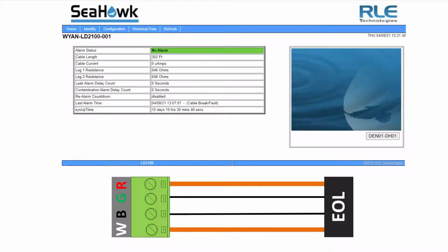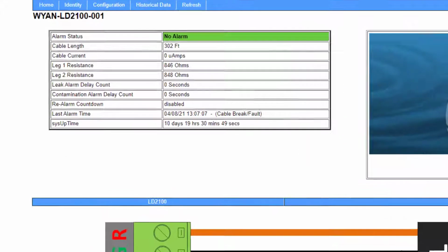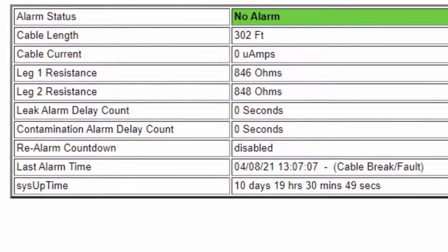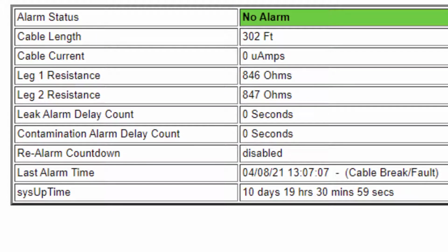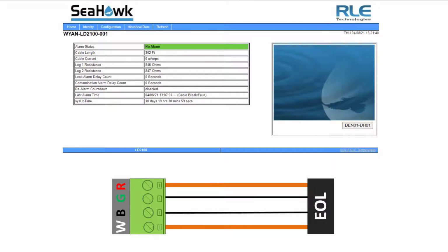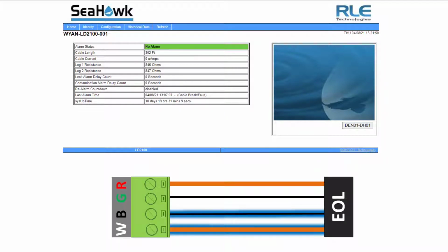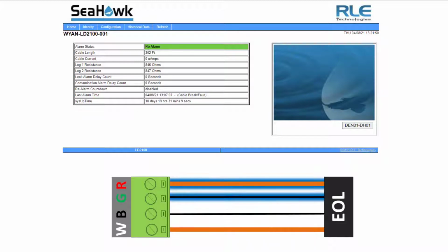So when you look at some of the menus, you'll notice that there's a leg 1 resistance called out, a leg 2 resistance called out. Then if you look at the leader cable, you'll notice there's a white, a black, a green, and a red lead hooking into that controller. So your leg 1 is the white and the black lead. Your leg 2 is the green and the red lead.